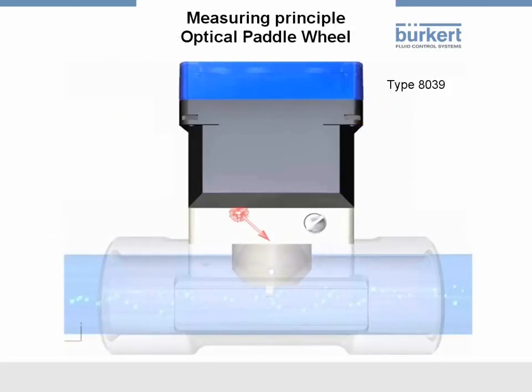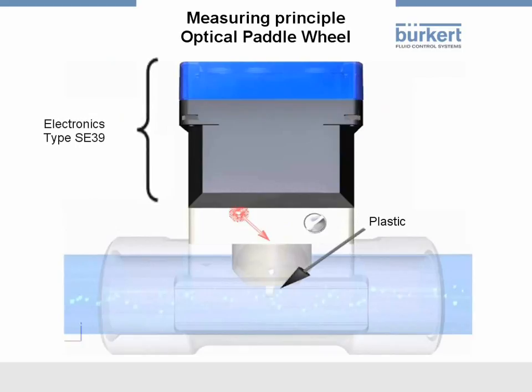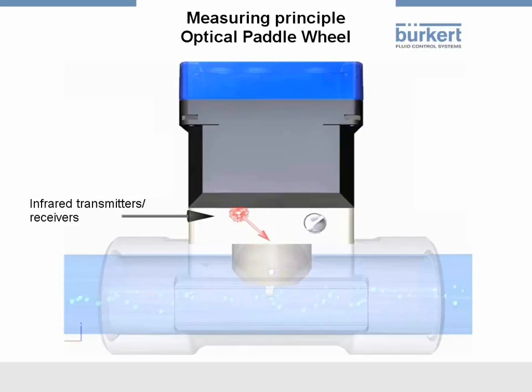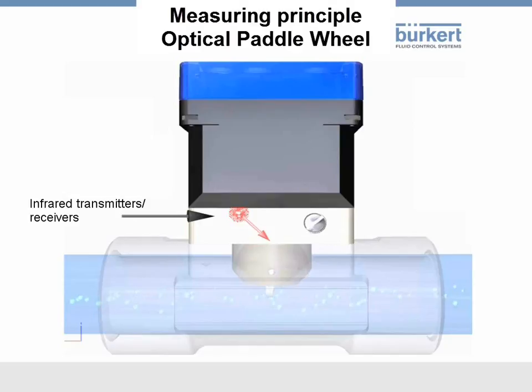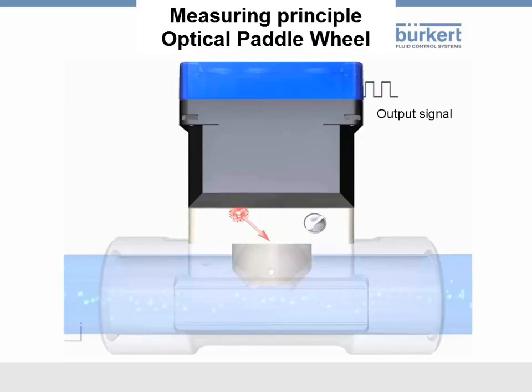In optical signal detection, the paddle wheel is made of plastic. The electronics housing is outside of the medium area, directly above the sensor. It contains two infrared transmitters/receivers, which are separated from each other by an infrared impermeable plastic. These two infrared transmitters/receivers detect the rotation of the paddle wheel, and the integrated electronics convert the reflected infrared signals into a rectangular frequency signal.